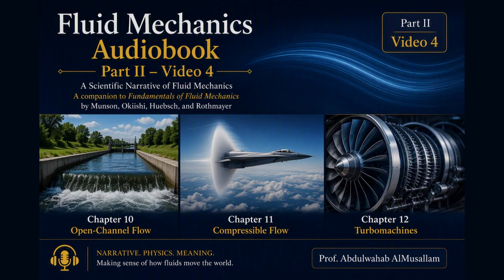Cavitation is a critical pump concern. If pressure near the pump inlet falls too low, vapor bubbles form and later collapse in higher pressure regions. This can damage surfaces, reduce performance, and create noise and vibration. Net positive suction head is a way of expressing whether the inlet conditions provide enough pressure margin above vapor pressure. Similarity laws allow turbomachines to be compared and scaled. Dimensionless parameters organize performance data and allow model tests to inform prototype design.